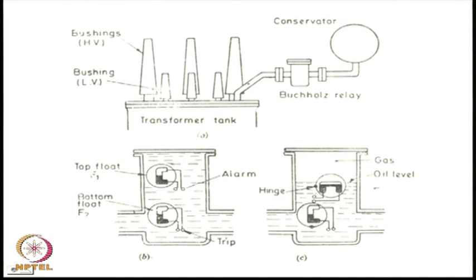The transformers are also to be provided with sufficient protections. The electrical protections are normally provided by relays. Here is one arrangement that provides protection against transformer overcurrent or short circuit. This is provided by what is called the Buchholz relay. This figure shows the construction of a Buchholz relay.